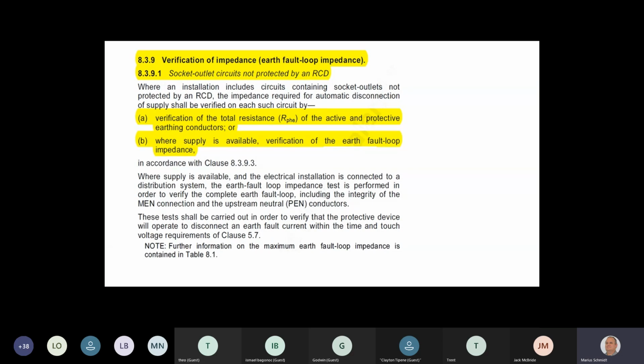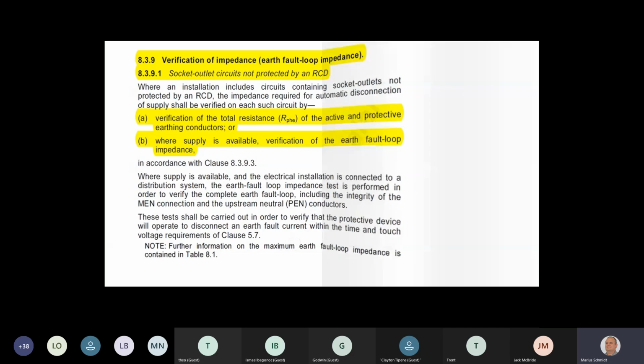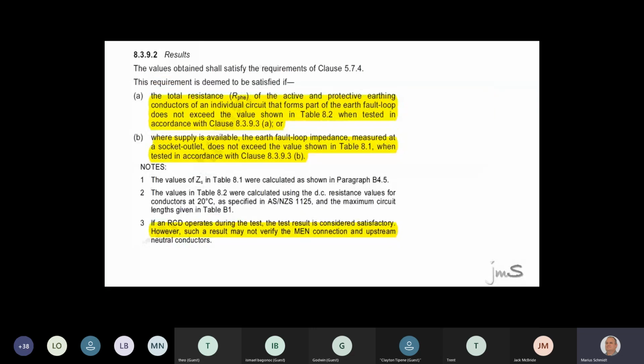Then we read further. The impedance test can be done live or dead. If you read A, dead. If you read B, live, where the supply is available. If you read note number 3, if you do an impedance test on a circuit where there's an RCD connected and it trips the RCD, your circuit is okay. Because is it true that an RCD must operate faster than an impedance tester? Example, 0.4 of a second versus 0.3 of a second. Cool. And here we go.